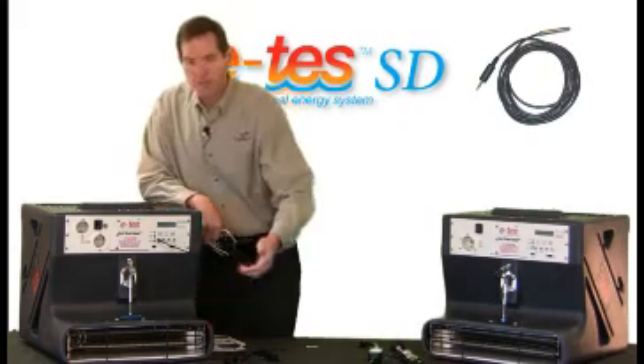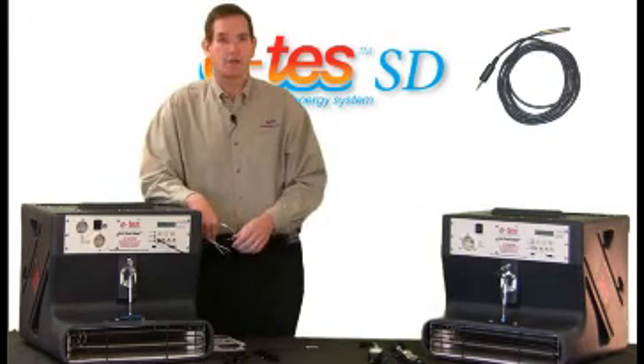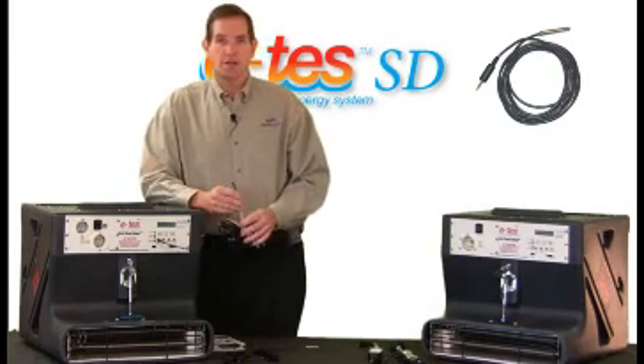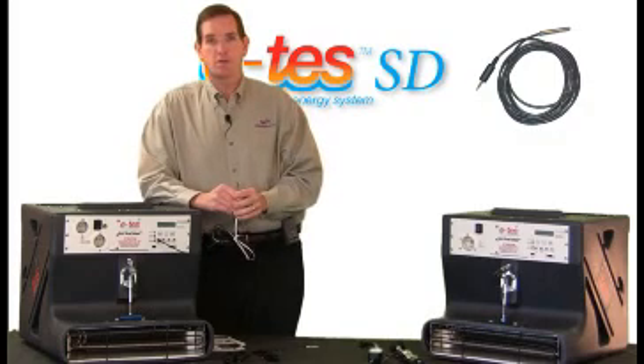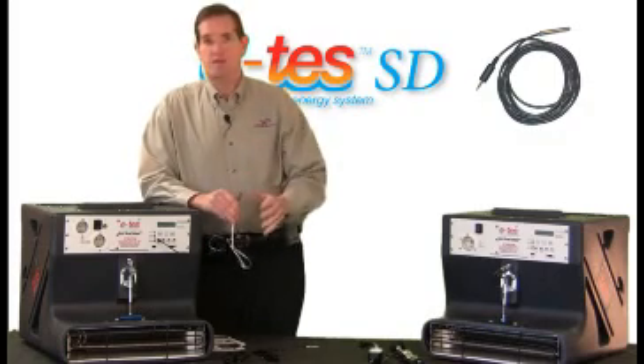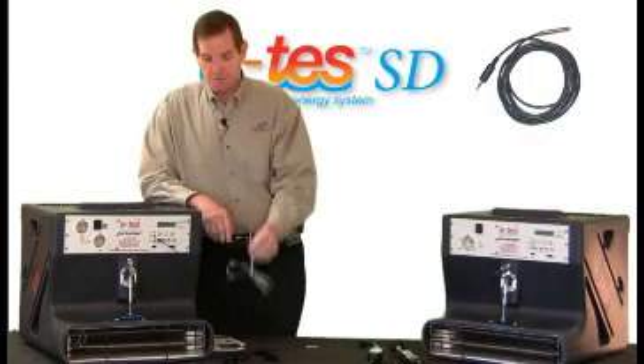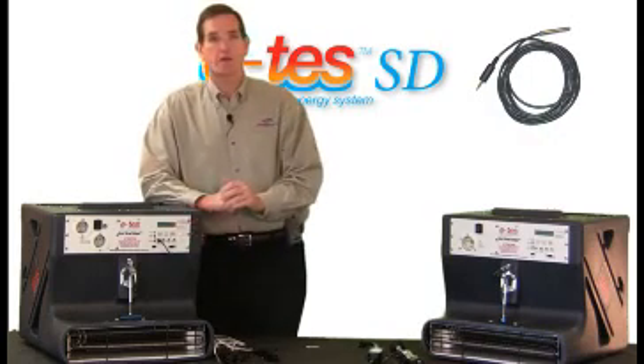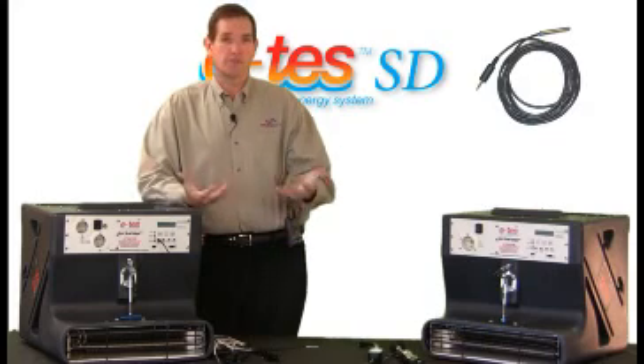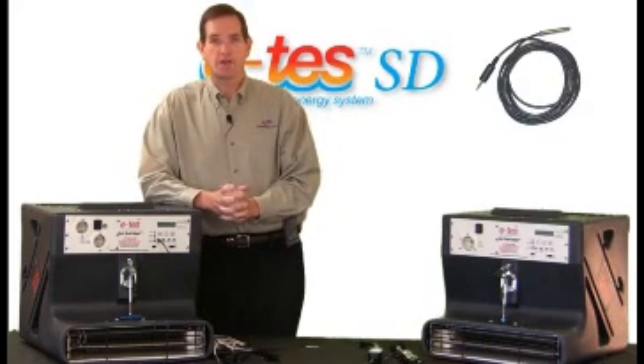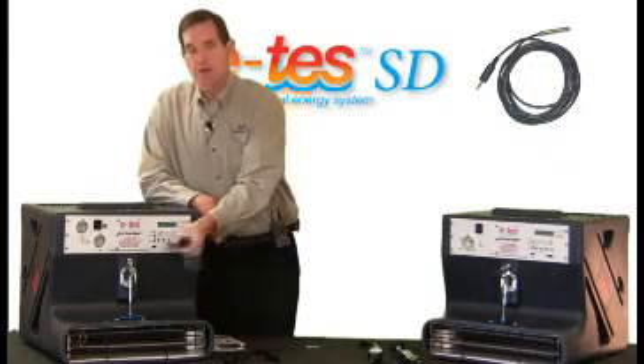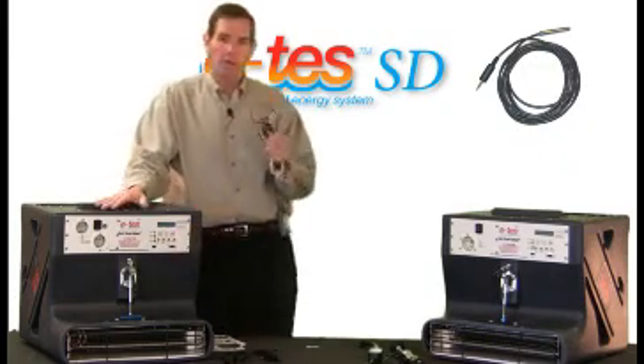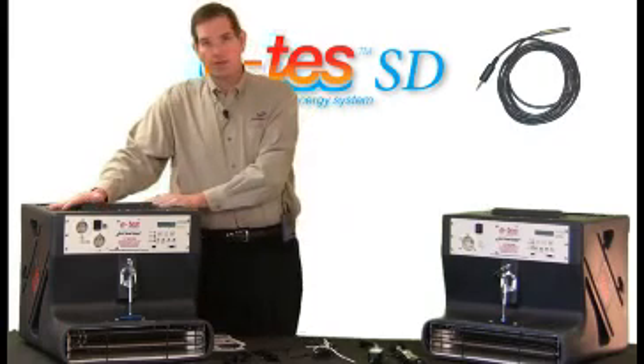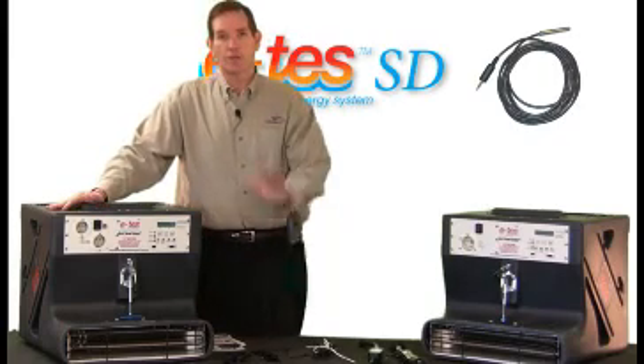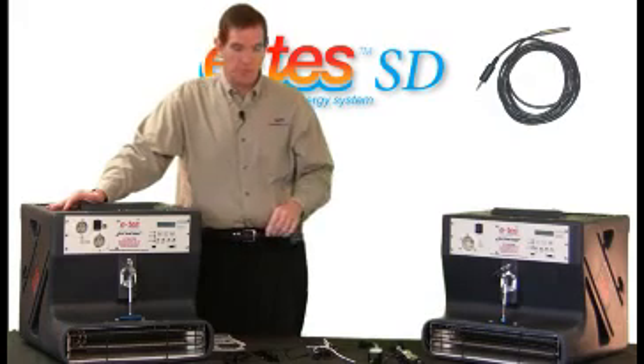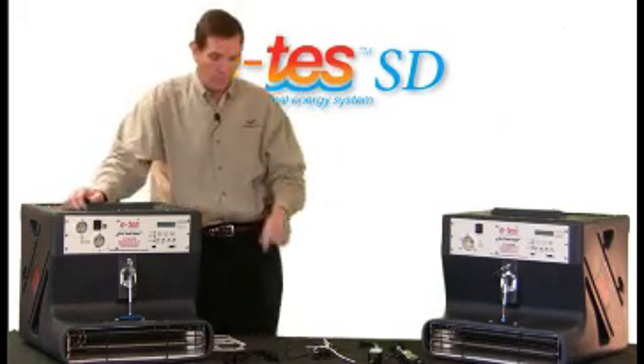Coming out the snout of these boxes, you might have 100, 120 degrees, and even more in some situations. But if you don't want the ambient air to get too warm, if you're pumping under carpet, under plastic containment, or just in the air, you can actually set the temperature sensor on your controls here that will turn the machine on and off. For example, maybe you don't want the environment to get over 95 degrees. This unit will allow it to control the machine. It will also document the air temperature. Remember, I told you there's an air temperature built inside. This is a second unit, so you now have two air temperature sensors and readings that you can use.